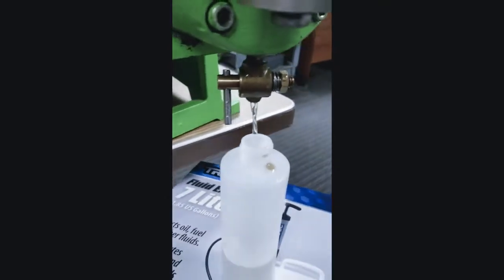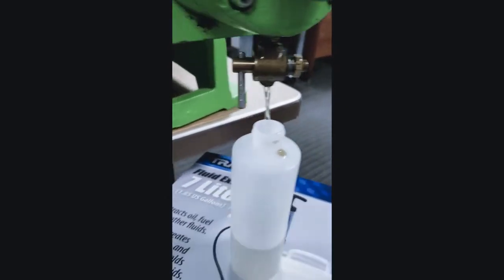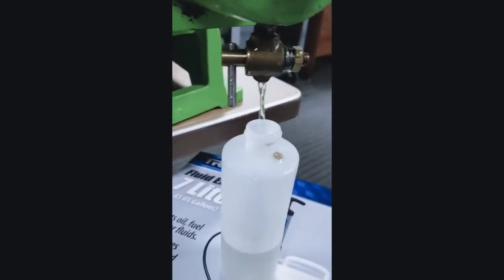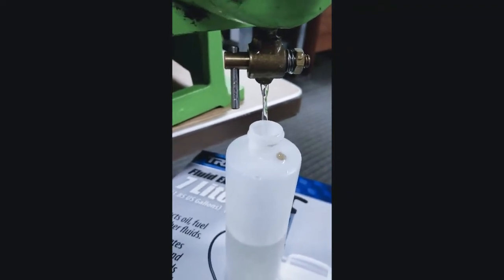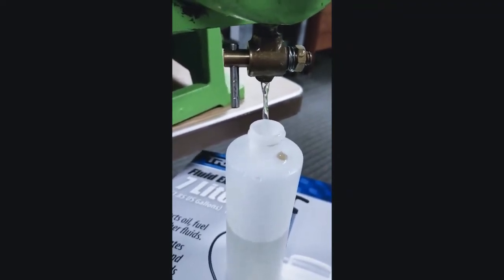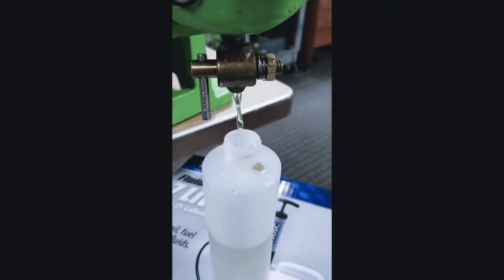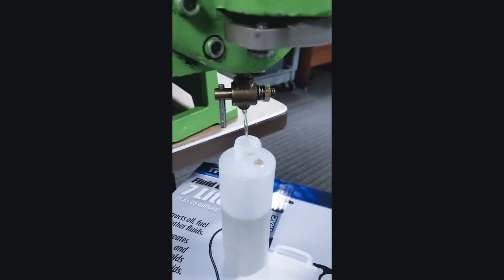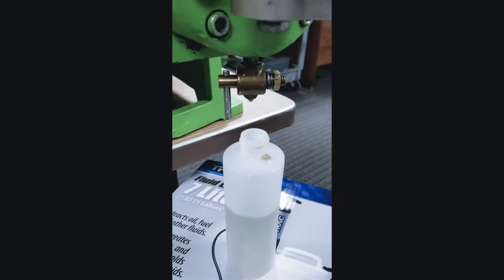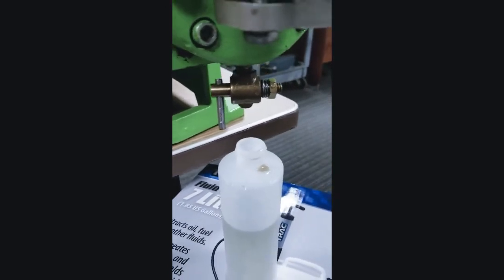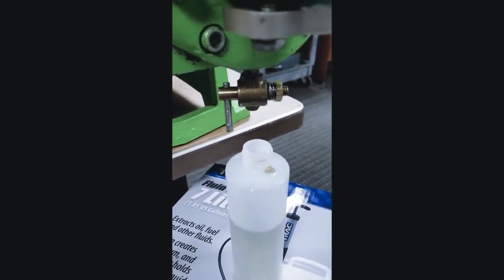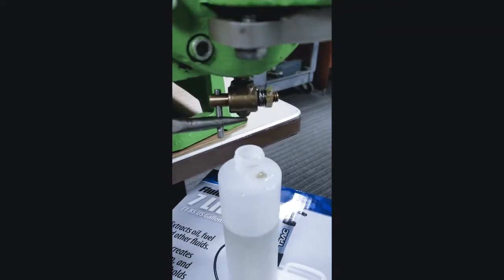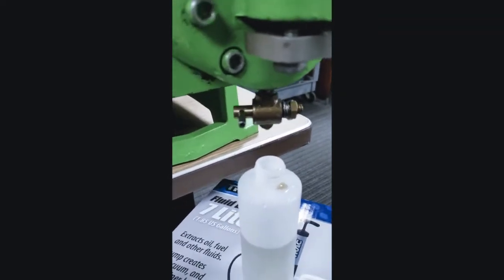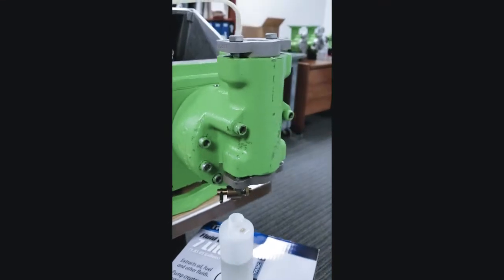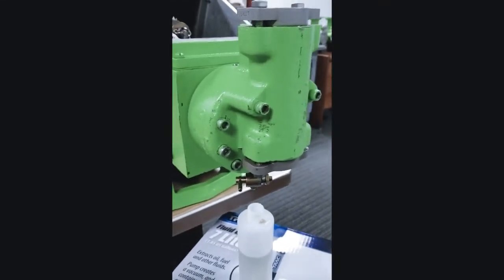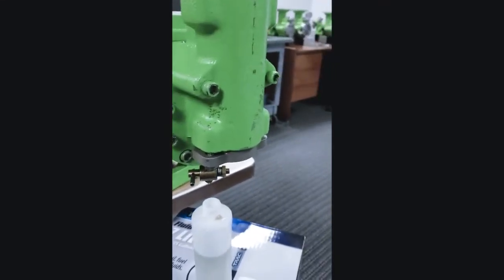If you don't have a small capture container, you're going to want to get one, possibly a bucket or a small pan or a drip tray, something to capture the fluid out of there. And you can see I've got a small 500 milliliter bottle that I'm using for this purpose. Okay, so once that's all drained, I'll close my valve again, and we're ready for the next step of removing the head bolts and taking the Hydratube head off of the pump.